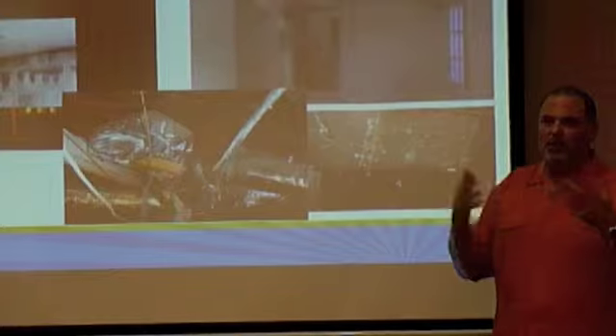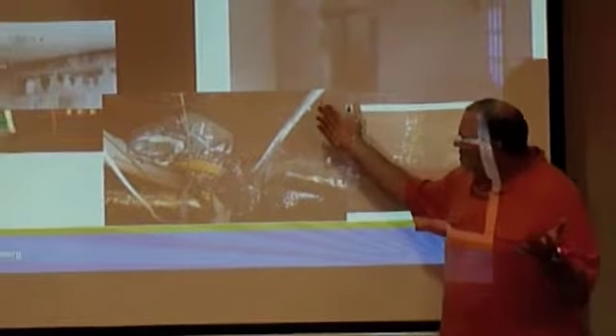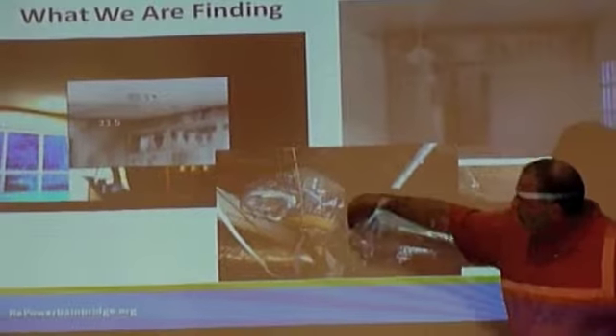It has a very low friction loss. You can insulate them and you can air seal them if you seal them properly with mastic and not tape. We don't like tape because it dries out over time and falls off, and the air is going to go to the path of least resistance under pressure. Remember, we've already got resistance in it because it's a slinky, but now besides resistance in it, we've got drapes over this one, we've got running over this one, we've got to go over the top of this one. Oh, by the way, let's just seal it up and put duct tape on it.